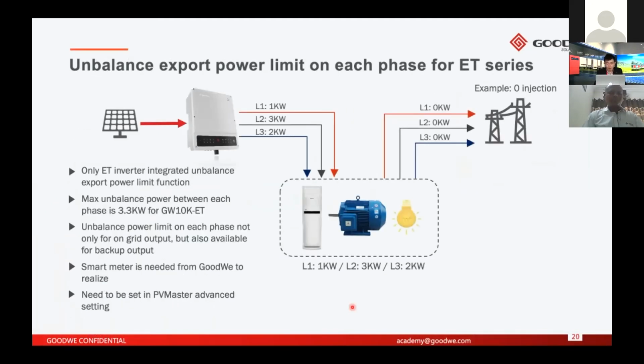And for our hybrid inverter, we also have one premium feature: unbalanced export power limit on each phase. Just now I already mentioned that in the Czech Republic, the grid company measures the power consumption on each phase. So the customer wants to do the export power limit on each phase, but they also want the inverter to output the maximum power to the loads.